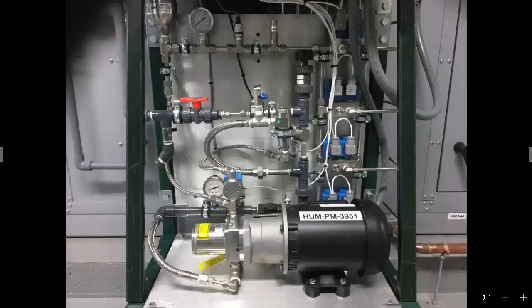So let's talk about troubleshooting a little bit. This high pressure side is not quite as straightforward as the low pressure side would be. There's a lot more that can happen. What you're up against as far as troubleshooting is a little different because you're dealing now with the pump itself, the pump doing its discharge into the piping, and what the pump does as far as its speed.